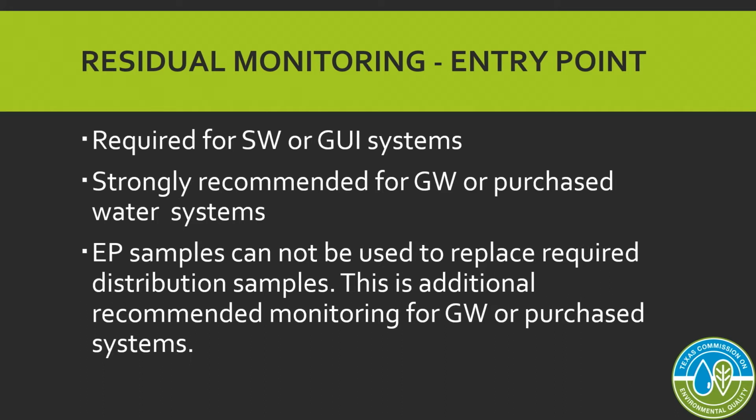For this disinfectant monitoring, for surface water and GUI systems, there is required monitoring for the disinfectant residual at the entry point in addition to the distribution system. However, I would highly recommend, regardless of source, that you do entry point samples, because whenever you do distribution monitoring for your residuals, that's telling you the end of the story. If you're not measuring your disinfectant leaving the plant, you don't know where you're starting. You don't know how much usage you have in your distribution system. So even if it's not required, I highly recommend you know what's leaving your plant at what levels, even if you're not reporting that to us.